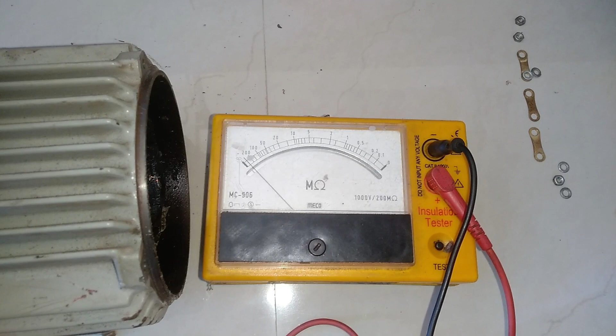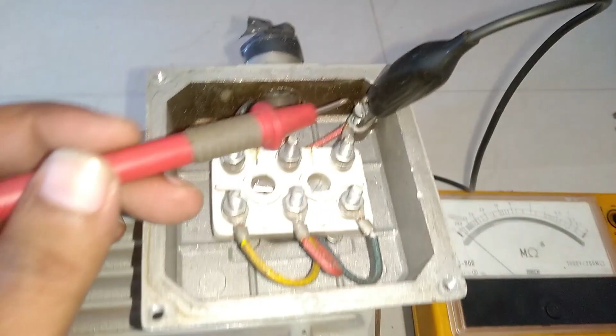As we all know, this is an insulation resistance tester, or in short form we call it a Megger. With this meter we actually see if the winding is shorted with the body or with the metal part, its core or the body. It gives us a value of the insulation strength of the winding with the metal body, the core and the stator body. So now we connect the black probe to the earthing bolt, the earthing screw. As we know, this screw is electrically connected with the whole stator body, the core plus the metal body.